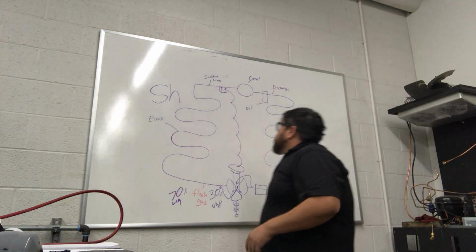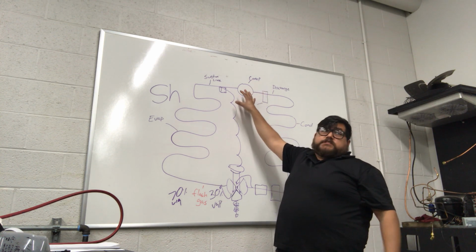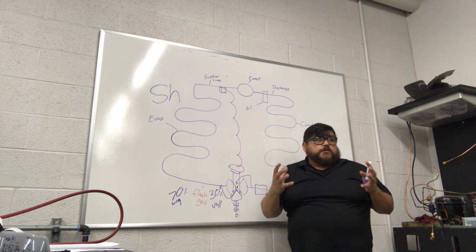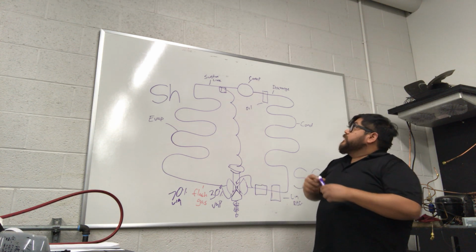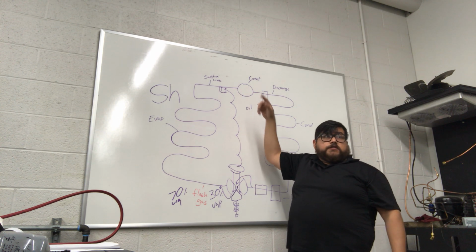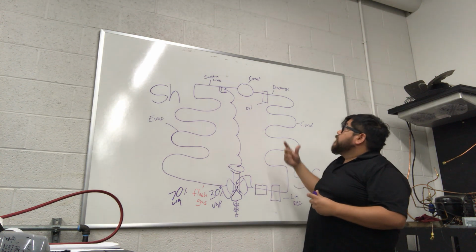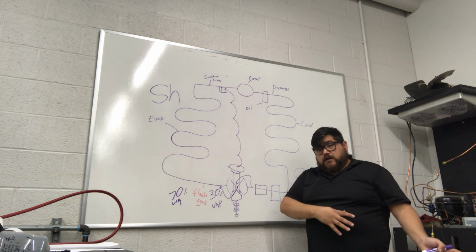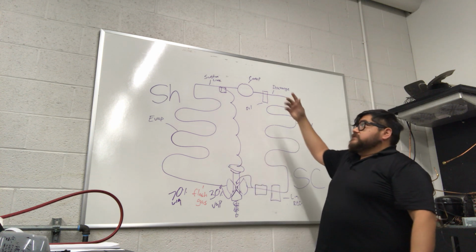The oil over here on the compressor and oil migration. I don't think you really put too much into it. Yeah. So the compressor, once it's in an off position and it cools down too much, somewhere around 55 degrees, that refrigerant is going to want to mix with the oil and then condense inside of that oil crankcase. So what we do is we put in a heater to keep that oil warm, so when we go to startup, we don't have that mass expansion, we don't have that foaming. So once we get rid of that foaming, we're not going to have as much oil migration. What is oil migration? The oil starts to foam, and it gets taken out with the refrigerant as it's being compressed. And then it moves throughout your system, migrating throughout the system.